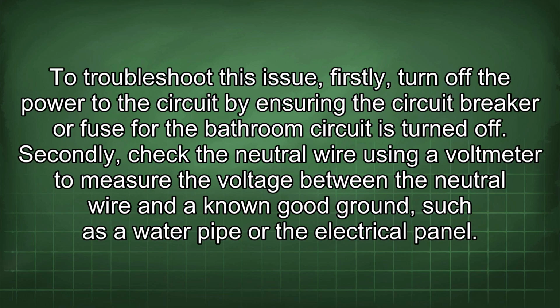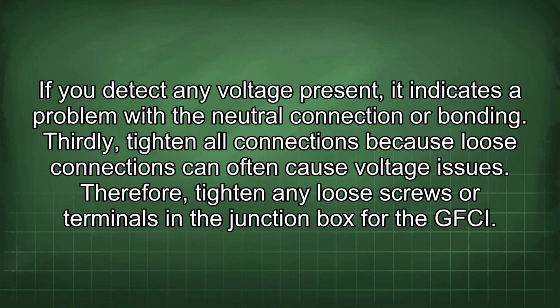To troubleshoot this issue, firstly turn off the power to the circuit by ensuring the circuit breaker or fuse for the bathroom circuit is turned off. Secondly, check the neutral wire using a voltmeter to measure the voltage between the neutral wire and a known good ground, such as a water pipe or the electrical panel. If you detect any voltage present, it indicates a problem with the neutral connection or bonding.